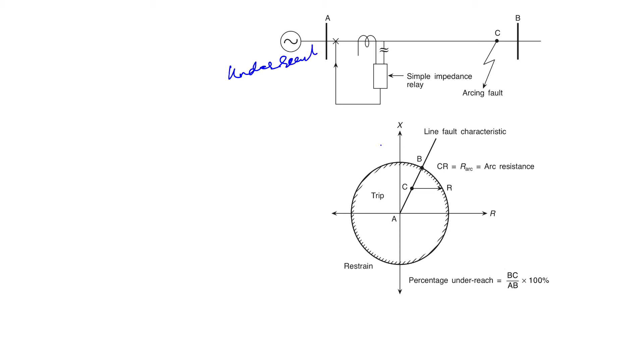Now we will discuss the directional property exhibited by the simple impedance relay. The reach of the simple impedance relay is independent of the phase angle between the voltage and the current at the relay location. So the relay does not possess the directional property. It does not have any directional property.